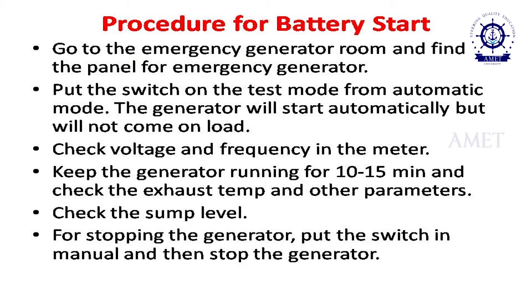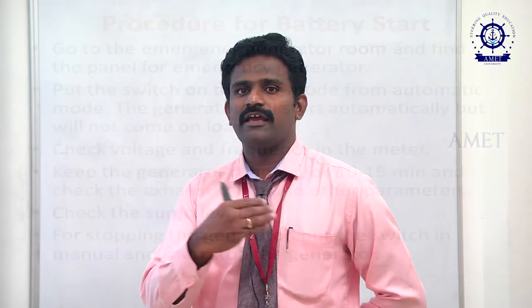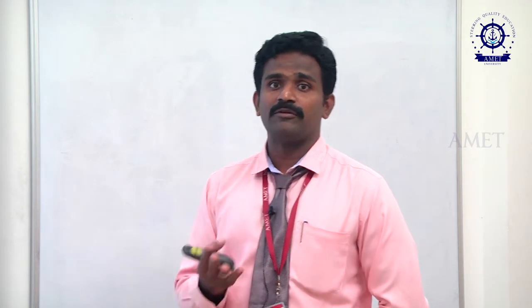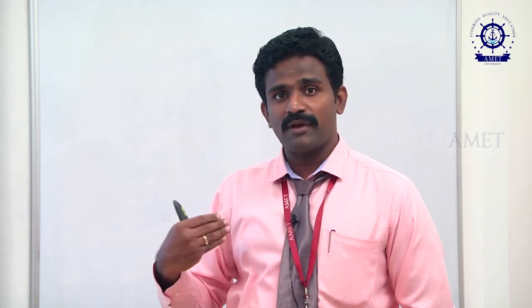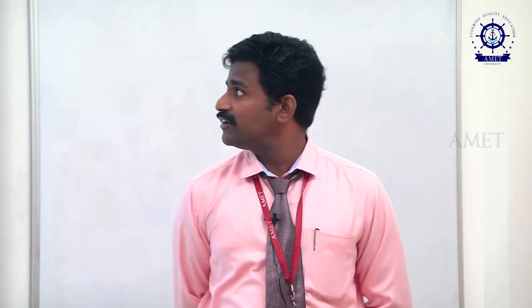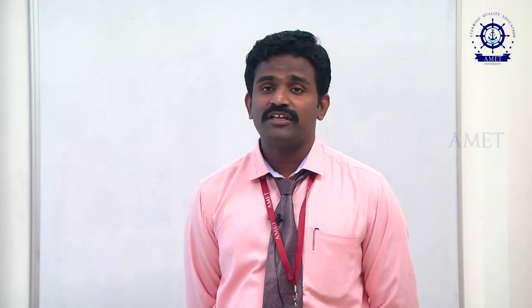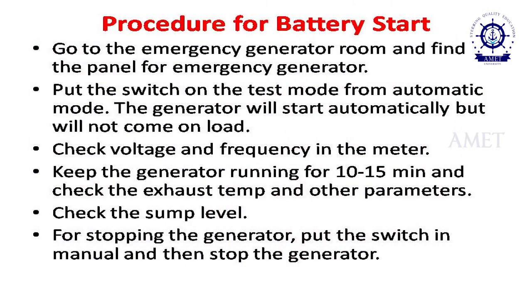First, we look at the battery start procedure. The procedure is very important and must be followed step by step. Go to the emergency generator room and find the panel. Put the switch from automatic mode to test mode. For maintenance testing every Saturday, we switch to test mode from automatic mode. There is a panel — in newer technology there is an LCD touchscreen on the power panel. In the switch panel, you can select automatic mode or test mode.